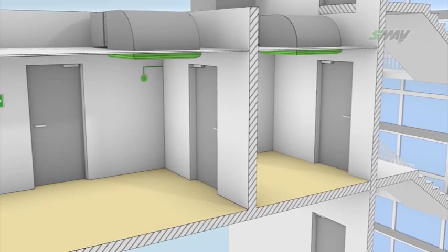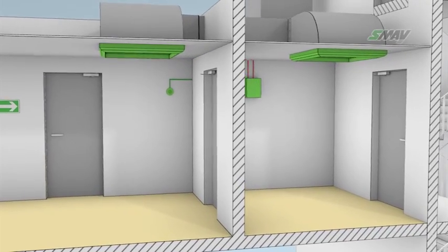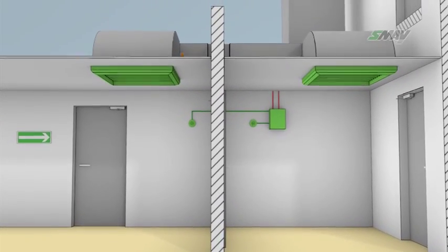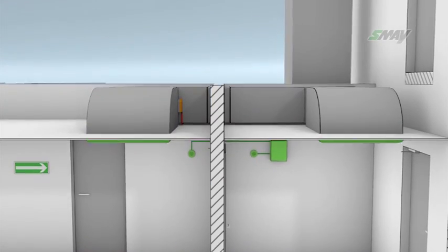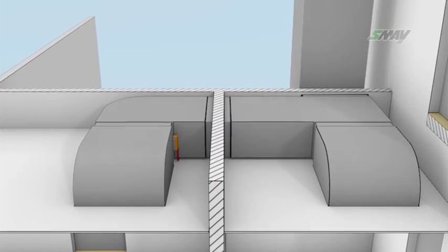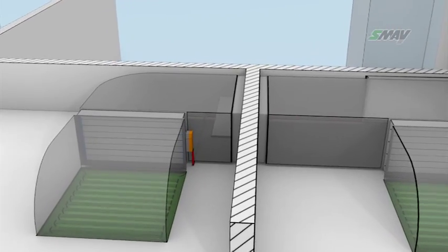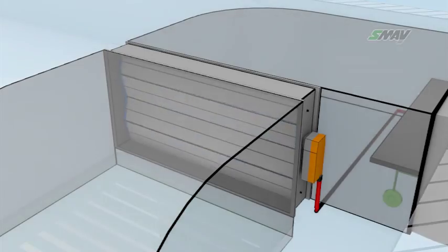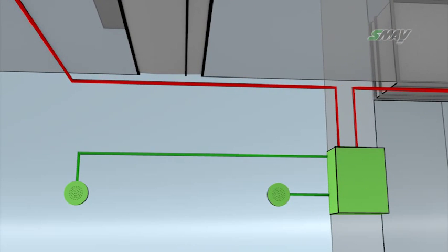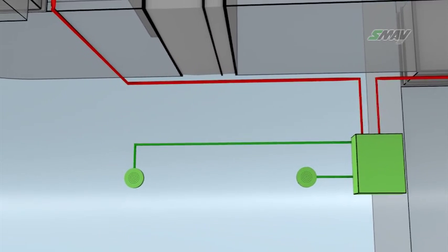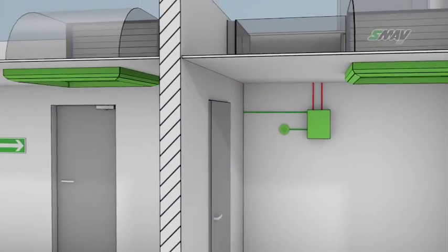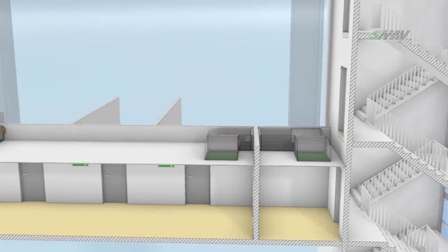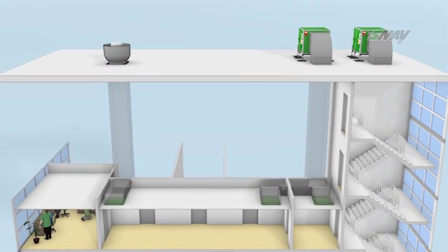An alternative solution to air transfer dampers is the use of an electronically controlled air transfer, which constitutes a duct with two branches, one to the firefighting lobby and the other to the corridor. Each branch is equipped with electronically and mechanically coupled multiblade dampers. The system also includes a regulator with two pressure measurement points, one in the lobby, the reference in the corridor. The proposed system is an answer to the smoke extraction air compensation problems for corridors operated by constant capacity smoke extraction fans.